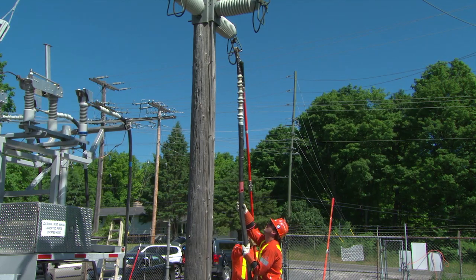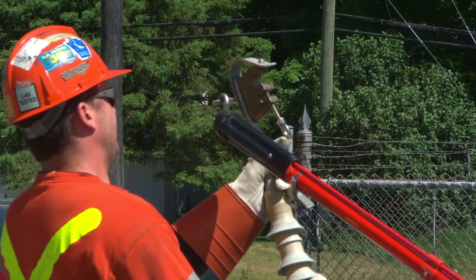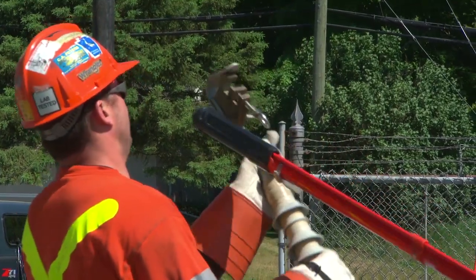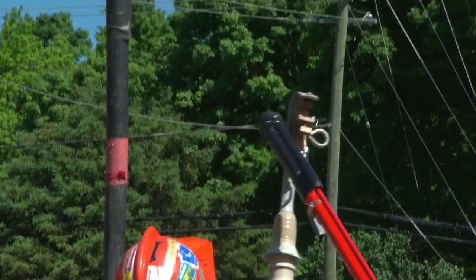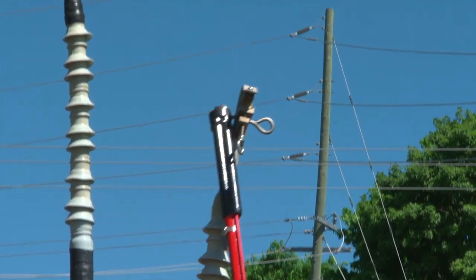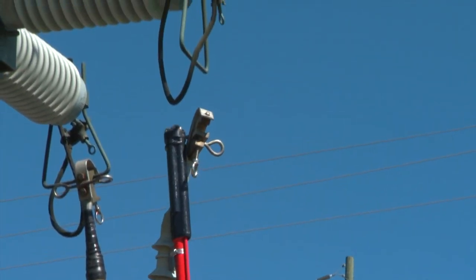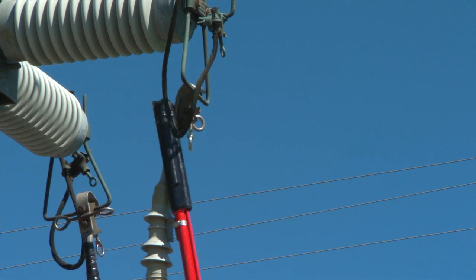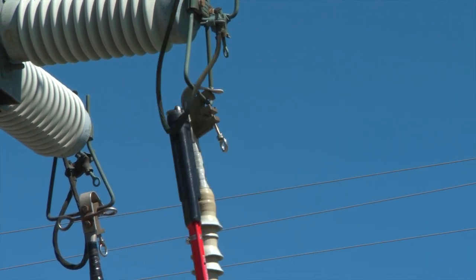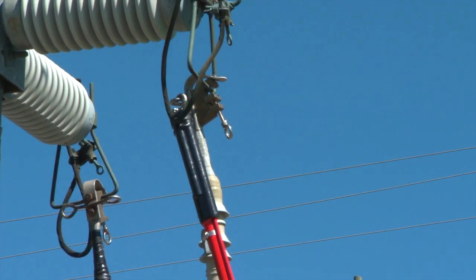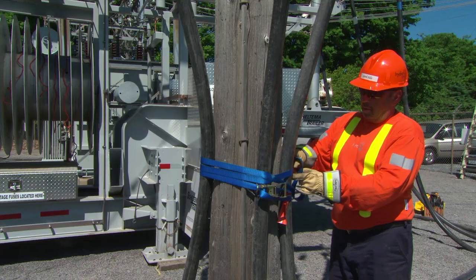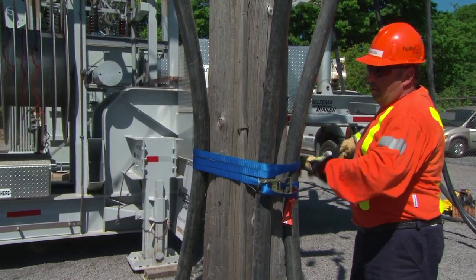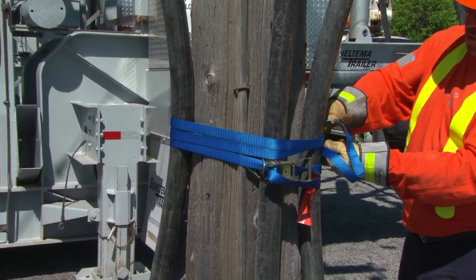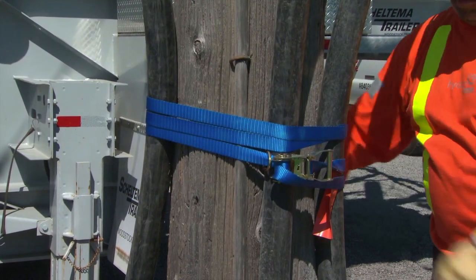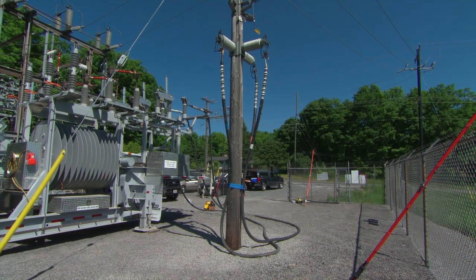Connect the high-voltage cables to the LC-MUS stirrups. Be aware that the 44 kV cables are significantly heavier than the low-voltage cables. Once the high-voltage cables are connected, secure the cables to the wood pole to help relieve tension on the connectors. Surrender the work permit.